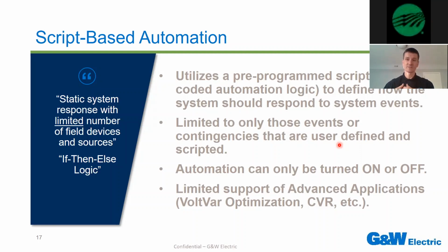What you get from that is a static system response to those contingencies and steps that have been programmed ahead of time. In other words, if a storm comes through and creates a fault or situation on that portion of your grid where you have that automation system running that wasn't thought of before during the design phase, and as a result wasn't programmed into the devices, it's not going to operate on it. So the system is only as smart as we are, so to speak, based on predefined contingencies. The last point is that with this type of automation, you can only turn it on or off.